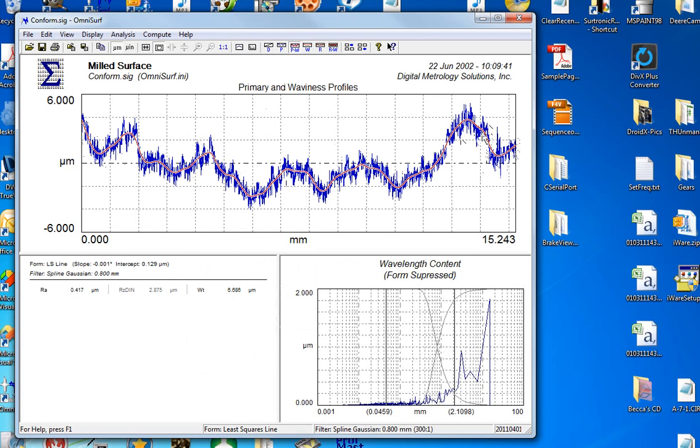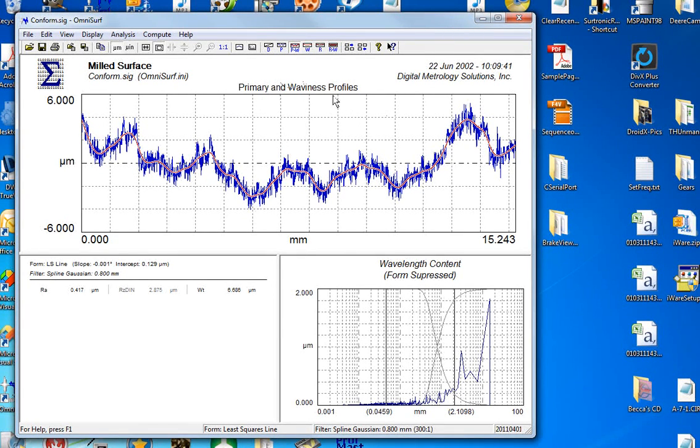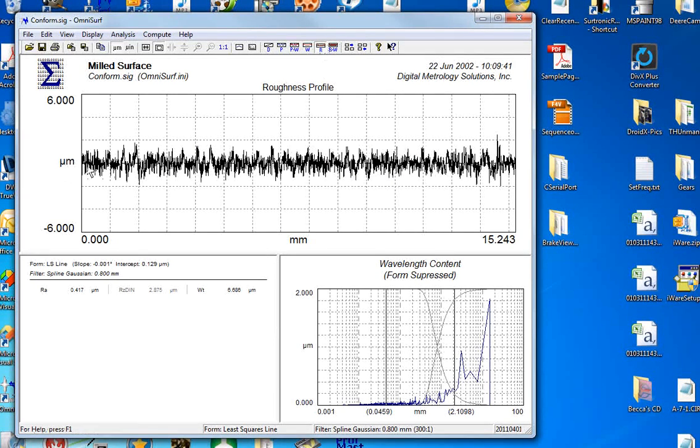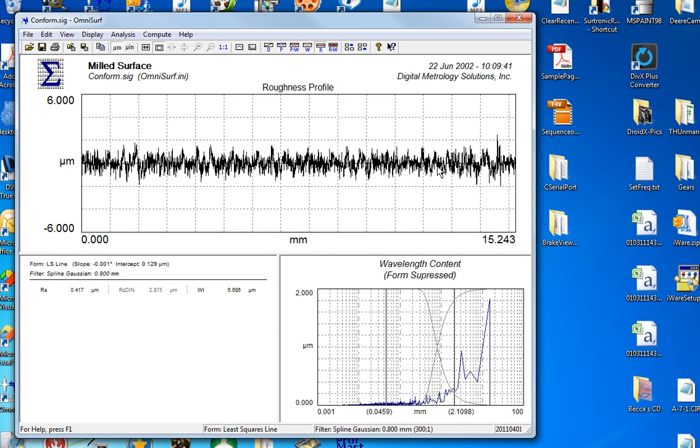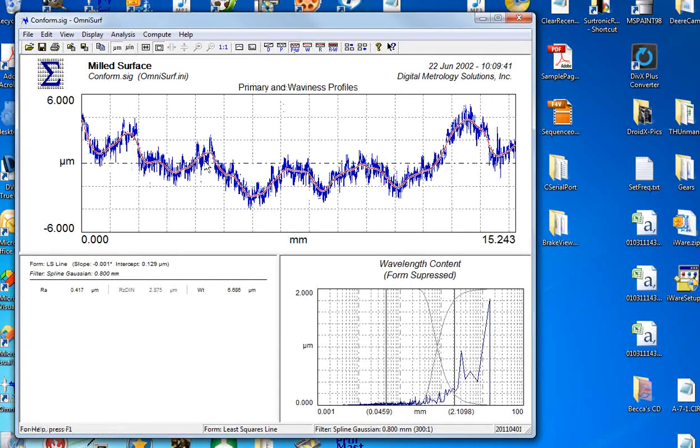Now people ask me, I'm measuring roughness, so why do you display primary and waviness? OmniSurf defaults to a primary and waviness display so you can see what your true surface looked like. Many people click on the little roughness button here on the toolbar and just show the roughness. That's okay if you're only interested in roughness, but in this case we see a very flat roughness profile when in reality the surface is not flat.